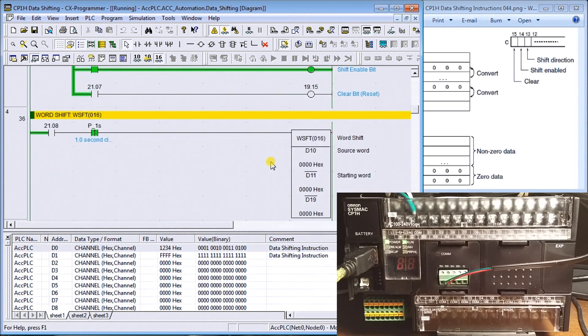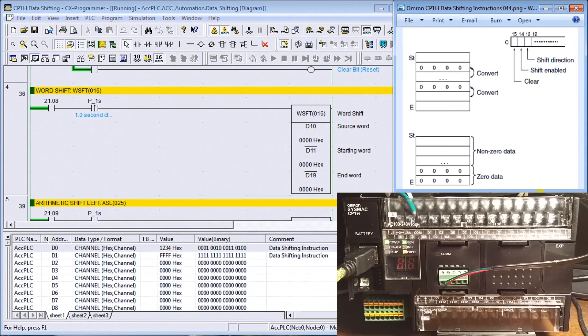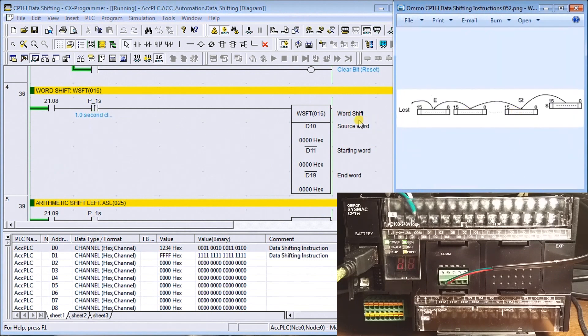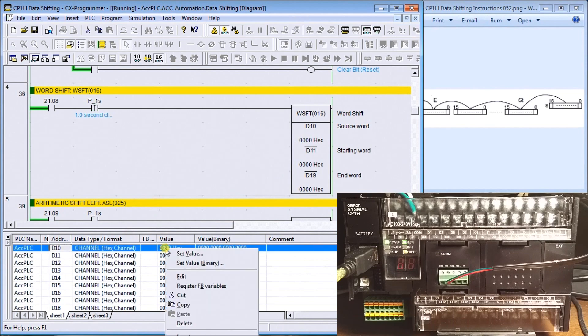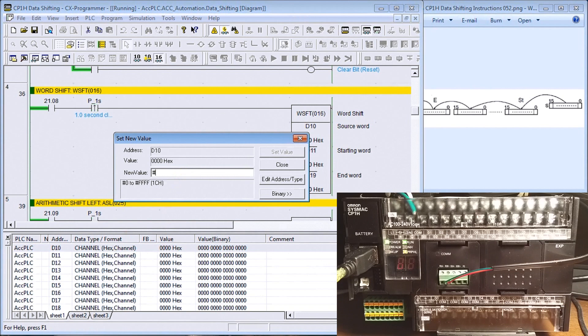The next instruction is a word shift. The word shift takes a source data word and moves it into the start of the register, and with each execution of the instruction it shifts one word down to the end. The last word is lost at the end of the shift register. In our case, data memory 10 is our source word and we're shifting from DM11 to DM19. We'll set the value 4321 as our source word.